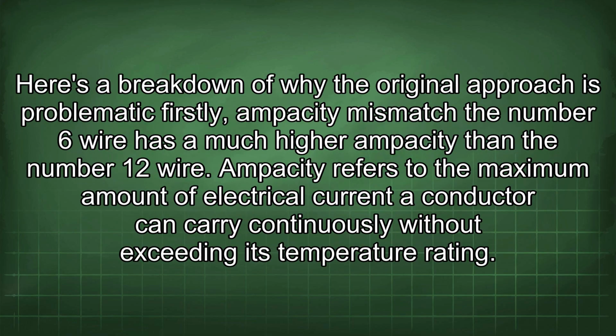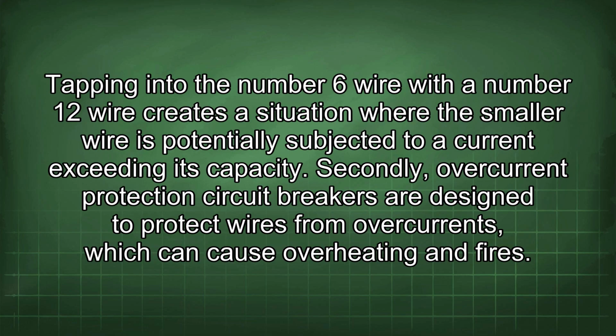Here's a breakdown of why the original approach is problematic. Firstly, ampacity mismatch. The number 6 wire has a much higher ampacity than the number 12 wire. Ampacity refers to the maximum amount of electrical current a conductor can carry continuously without exceeding its temperature rating. Tapping into the number 6 wire with a number 12 wire creates a situation where the smaller wire is potentially subjected to a current exceeding its capacity.